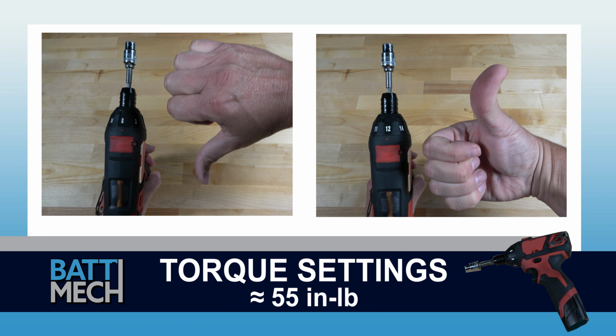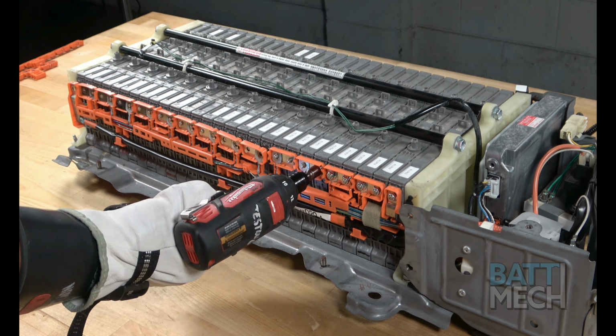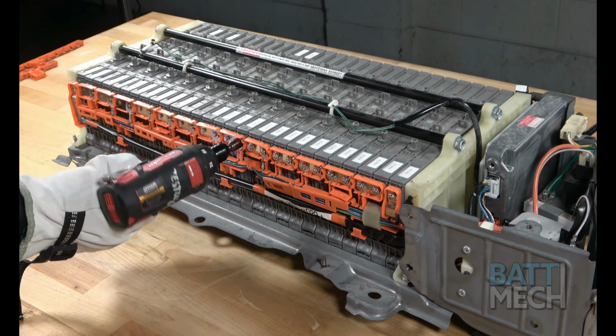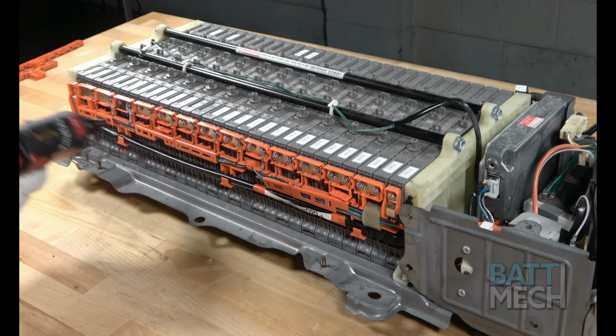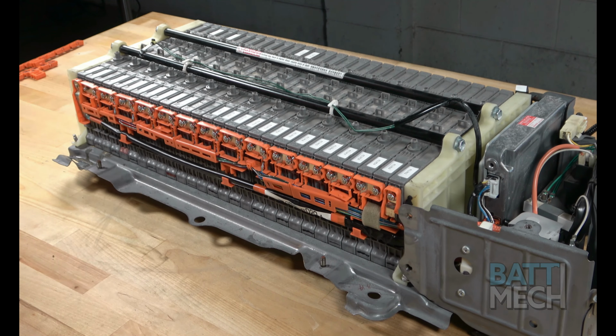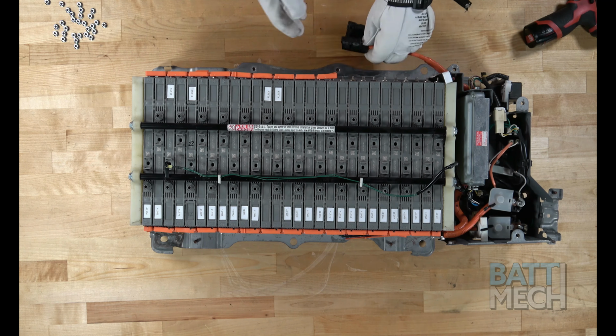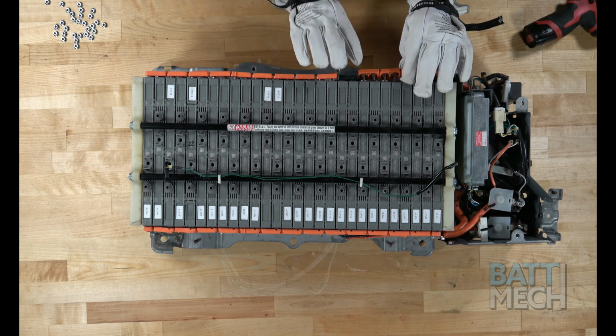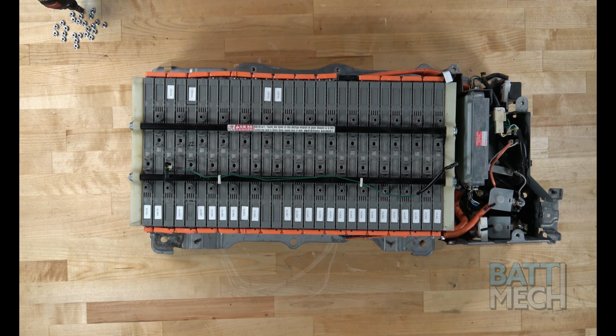Before attaching the wire harness, be sure your torque settings on your torque wrench are set to about 55 inch-pounds. If you don't follow these torque settings, you are likely to damage the terminals on the modules and will void your warranty. Never use max drill settings and never use an impact wrench. Now attach the wiring harnesses to the terminals using the brand new nuts supplied by BattMech. It's important that you use the new nuts as you will encounter issues using the old nuts. Repeat on the opposite side by attaching the wire harness to the terminals. Then attach the nuts to the terminals using the rest of the supplied nuts.